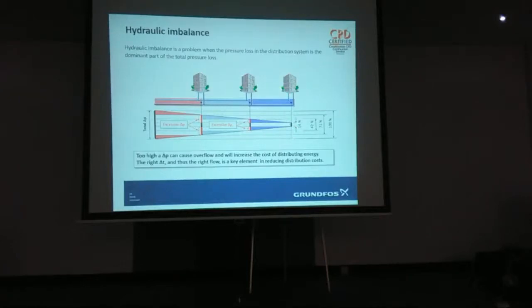Actually, in fact, they were feeding HRU units, and you need something like 50 kPa at the furthest HRU. They were actually pumping into the building, so that was going from here all the way down here up to the top floor to the end unit, needing 50 kPa. So that value there needed to be at least 50 kPa, but to achieve that, this needed to be 250 kPa, thereabouts. There are different ways and means of doing that.